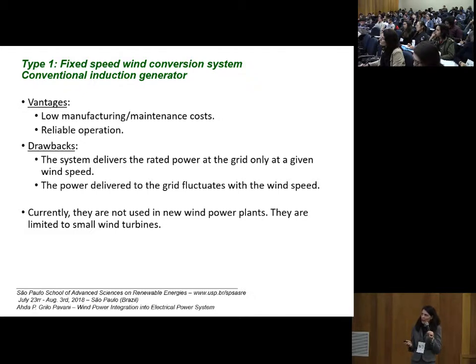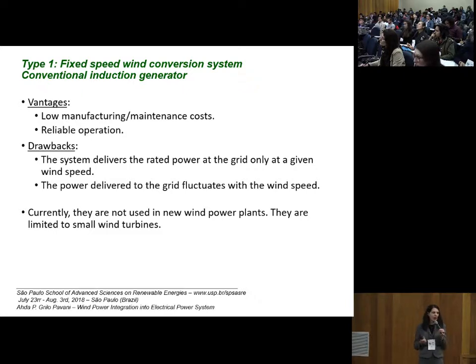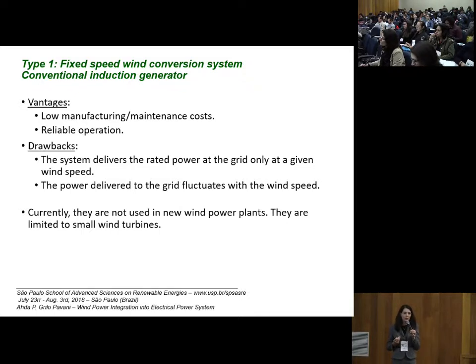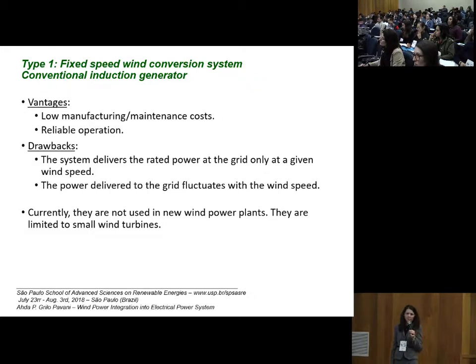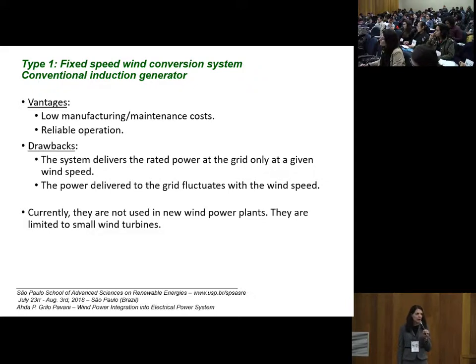The advantages of fixed speed wind conversion systems are low manufacturing and maintenance costs and reliable operation. The drawback is that the system delivers rated power to the grid only at one specific wind speed, and the power delivered fluctuates with wind speed — a significant problem for power systems. Currently, the use of this configuration is limited to small or medium-sized wind turbines.